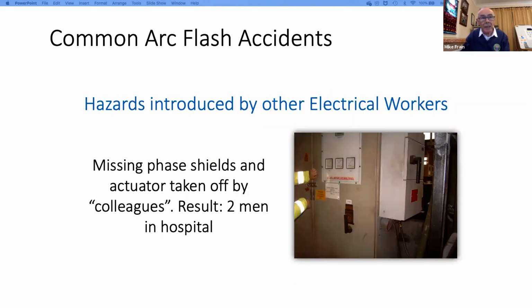This is one where I was called out on a Saturday. Two electricians were supposed to have come into this chemical works, actually, to vacuum this panel out. And there's a Saturday morning. I'll tell you a little bit more about Saturday morning working in a second, but it's when they could have the power off. So instead of locating the upstream protective device, they thought that they could get away with just operating the local isolator, which is on the front panel there. What they found was that it was just flopping around in the hand, and somebody had removed the actuator bar to the local isolator and also removed the phase shields.